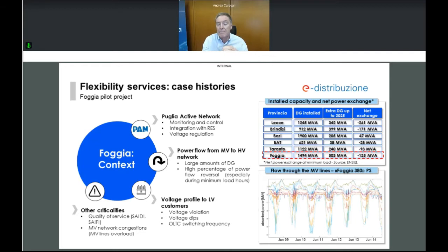The selection of the pilot site requires being characterized with numerical indicators designed to quantify and compare the candidate sites. A first measure used for the selection of primary substations is represented by the active power transits, measured at the interface with the high voltage network, and an indicator of the behavior is represented by the percentage of annual hours in a reverse flow condition.